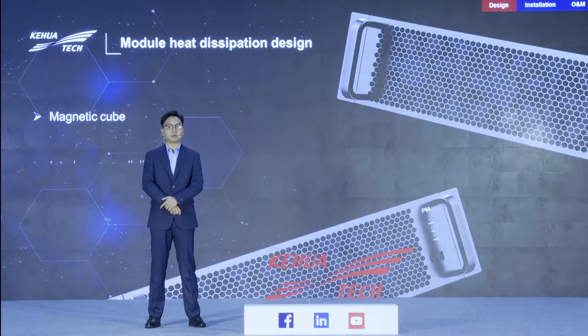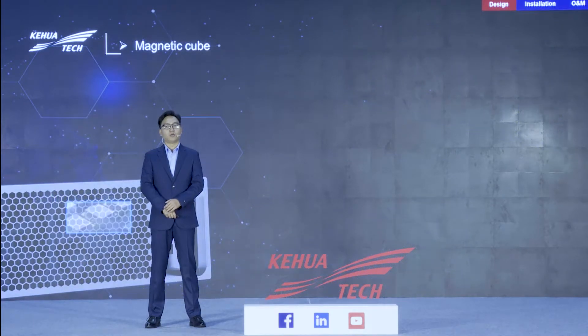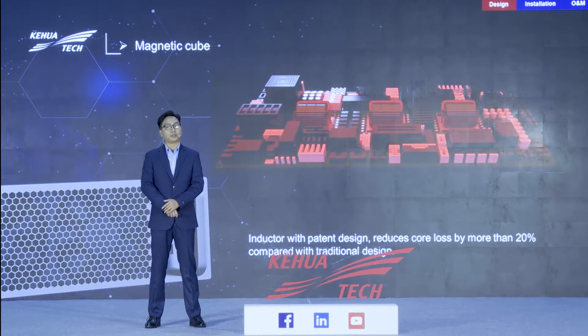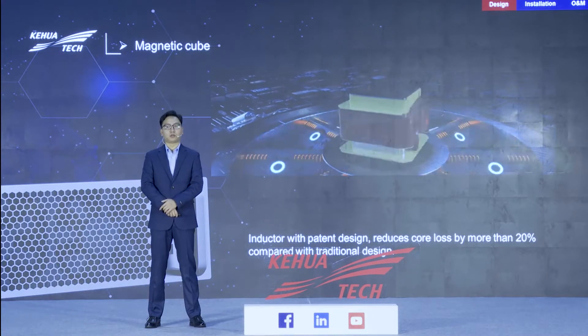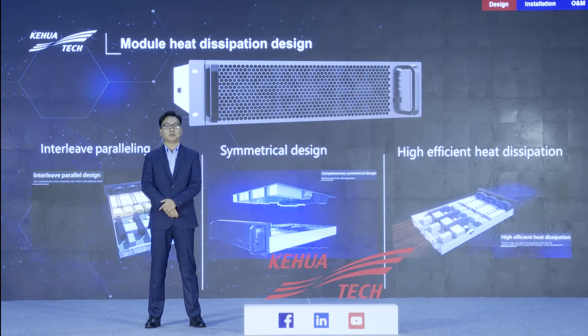When we do high power density design, module heat dissipation is a challenge. We use magnetic cube interleaved paralleling topology, symmetrical design, and high efficiency heat dissipation design to support the high power density. The magnetic cube patent design for the inductor can reduce core loss by more than 20% compared with traditional inductor design. We use interleaved parallel topology to reduce the voltage drop of the device and reduce the current ripple of the bus capacitor, which lowers the temperature of the IGBT diode and the capacitor.